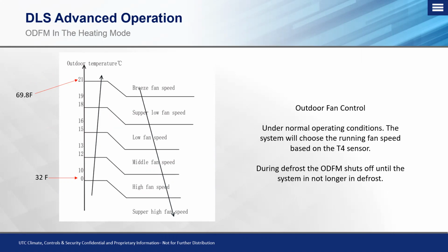During defrost, the outdoor fan motor shuts off until the system is no longer in defrost. If your fan motor is running in defrost, we might have other issues that we need to dig into. Just like any other defrost, that outdoor fan motor should not be running, because we need to get that coil nice and hot to properly defrost any excess ice buildup.